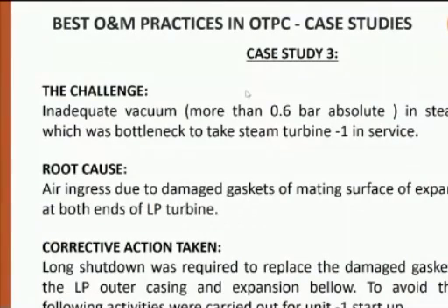Basically, one of our units underwent a major inspection, and we also took a medium inspection of the steam turbine. During the medium inspection, we opened the LP turbine, and after the overhaul, we assembled the turbine with the new gasket. When we went for taking the unit in line, we observed that the vacuum of the steam turbine condenser was more than 0.6 bar absolute, and there is an interlock. If the vacuum is more than 0.6 bar absolute, we can't take the unit into service. We can't give the gland steam to get better vacuum, so there is no possibility of opening the steam stop valve. So that was a bottleneck now.